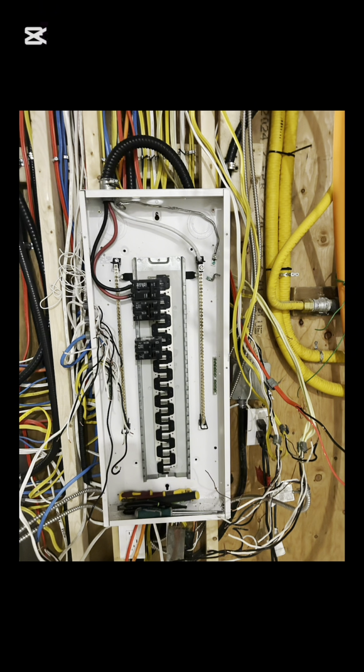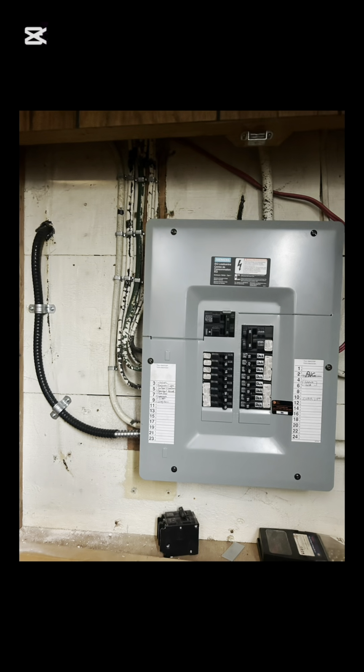So removing your bonding screw in the sub-panel is very important. Also, isolating your neutral bar is another key fix. Ground bars bonded to enclosures is one of the most important notes that you have to remember. And proper feeder with bonding conductors. Do these and you will pass your inspection.